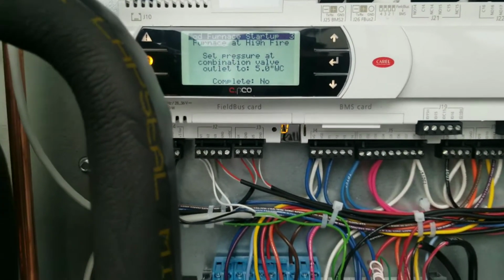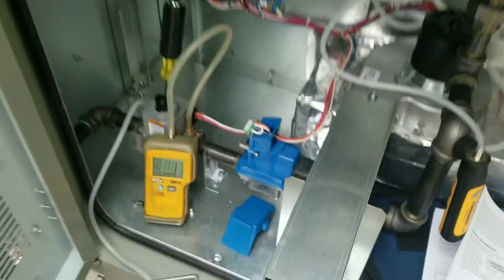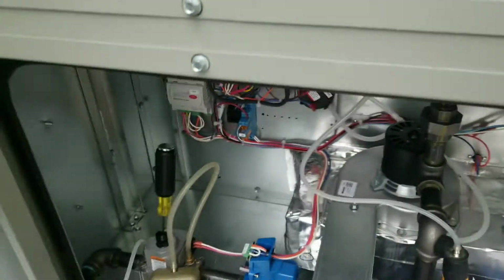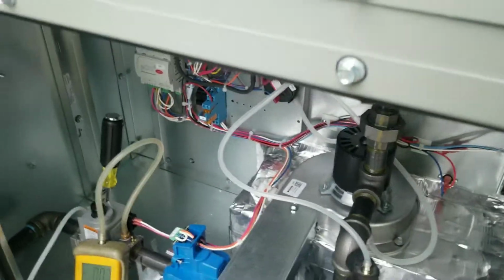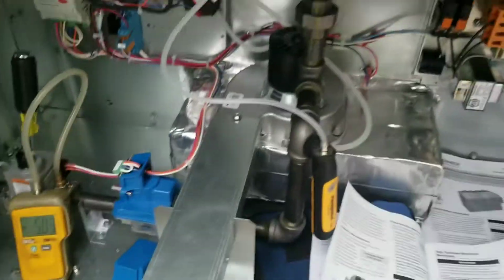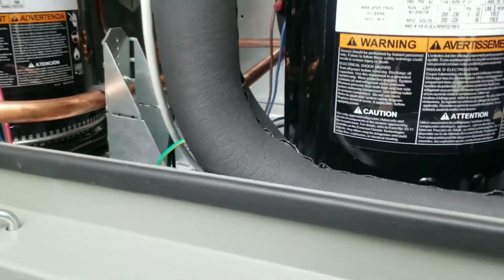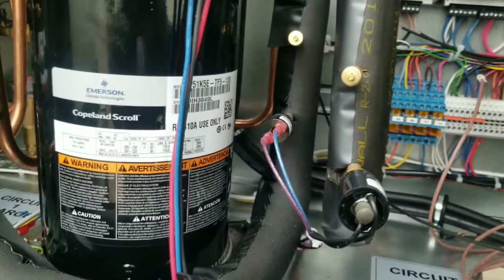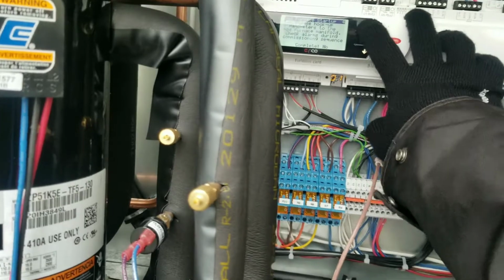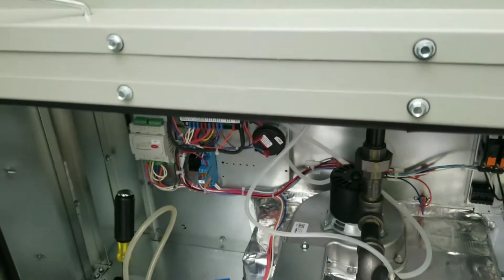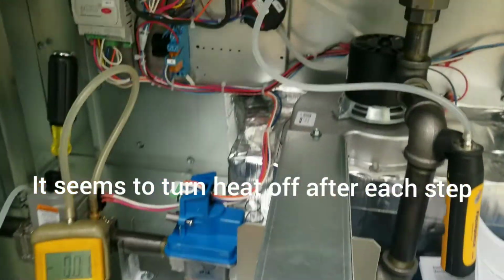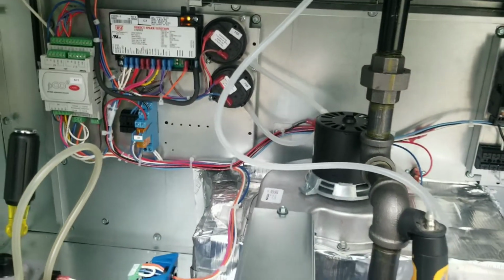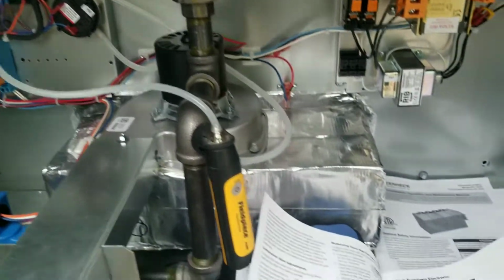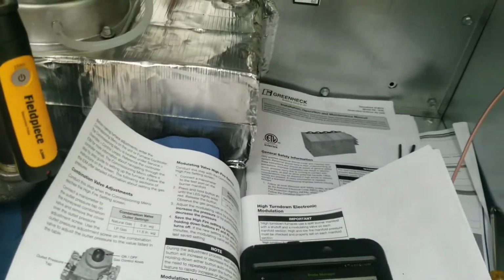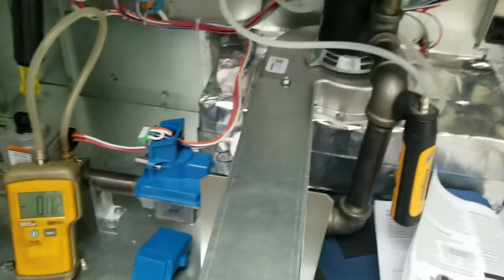So we've made some adjustments. We're in commissioning. That's my combo valve here at 5 inches water column. Let it do its pre-purge and cycle on. 5 inches water column. I'm gonna say yes. That's gonna go into a high fire after it's purged. Not the most efficient way to do this, I don't think, but that's what the control calls for. Let it purge.